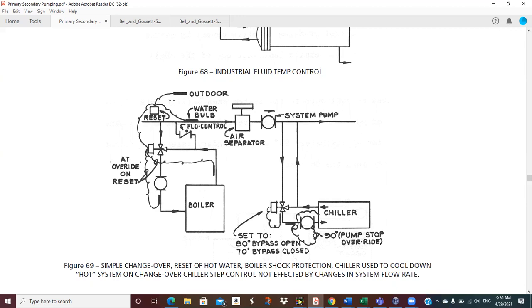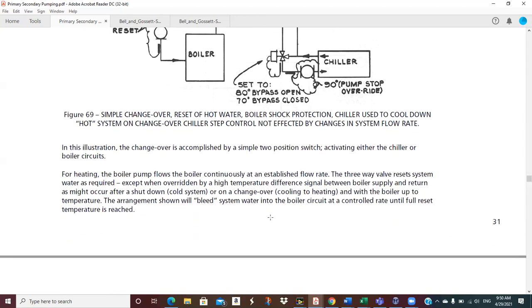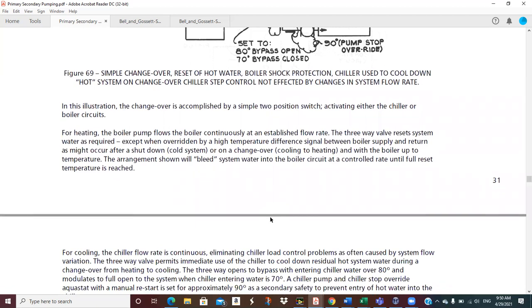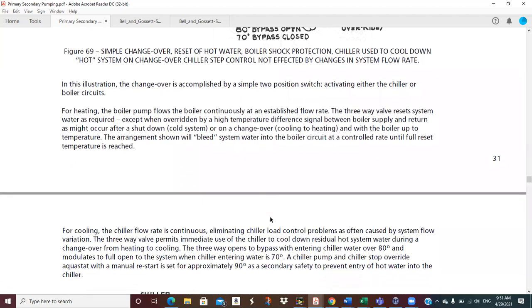I've got an outside air sensor over here. I'm doing reset, and I've got protection, you know, set to 80-degree bypass, 70-degree closed. So what they're saying is, if that water is 80 degrees or above, I'm not going to put it into my chiller. It's going to have to circulate until it cools down because I don't want to wreck my chiller. Let's see, I guess we'll go through a little bit of these notes.